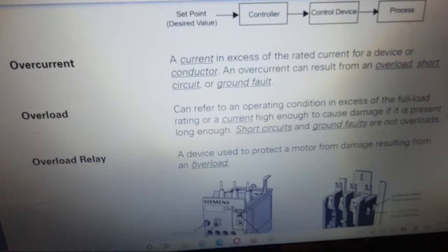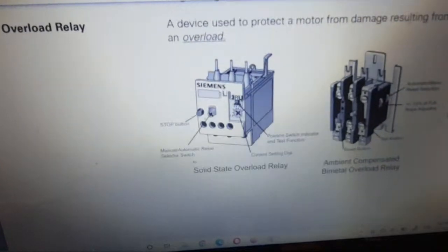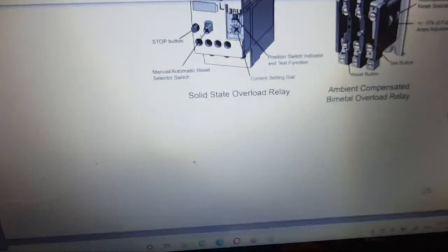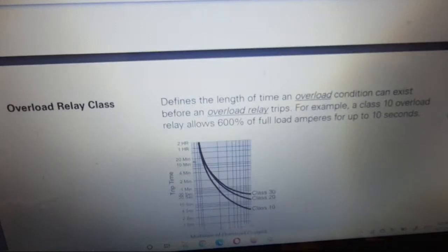Overload relay, a device used to protect a motor from damage resulting from an overload. Overload relay class defines the length of time an overload condition can exist before an overload relay trips. For example, a class 10 overload relay allows 600% of full load amperes for up to 10 seconds.